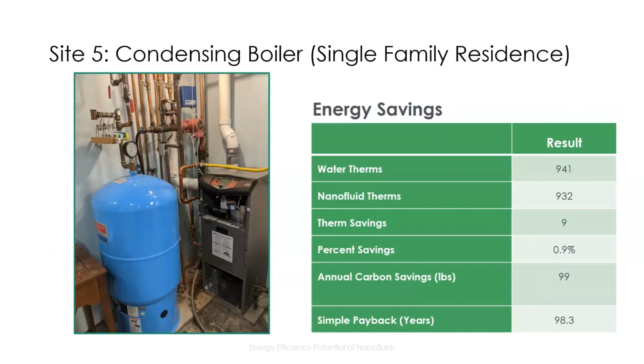The fifth site is a condensing boiler at a single-family residence. This boiler served 2 air handler coils, and as shown in the chart at the right, the data indicate that there is some small positive savings. Again, the site had a much simpler metering plan compared to the commercial sites, and we're pretty confident that there wasn't a major change in operating schedules at this residence, since it housed a retired couple across the whole metering period.